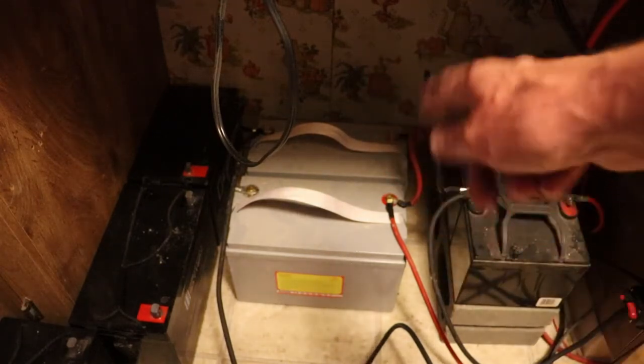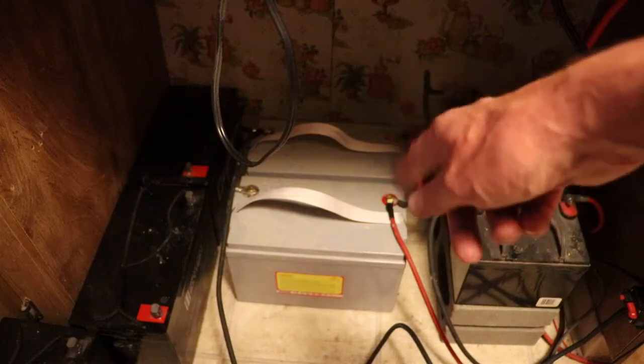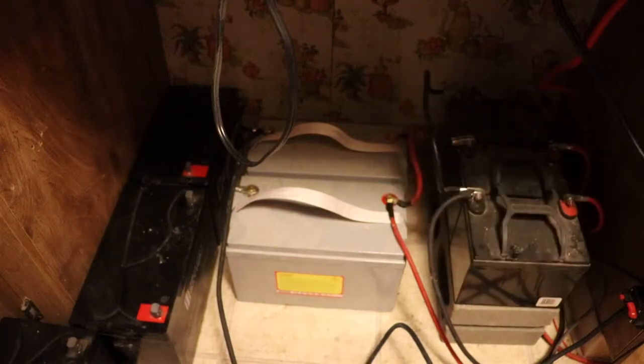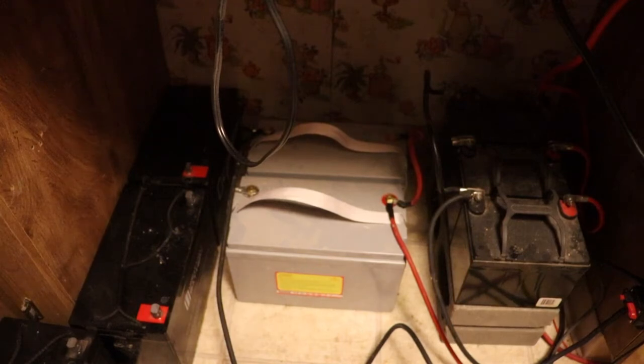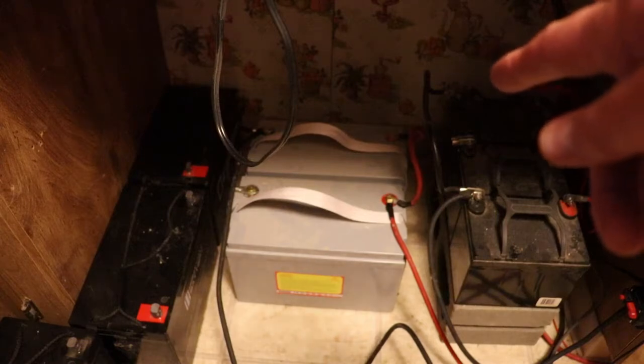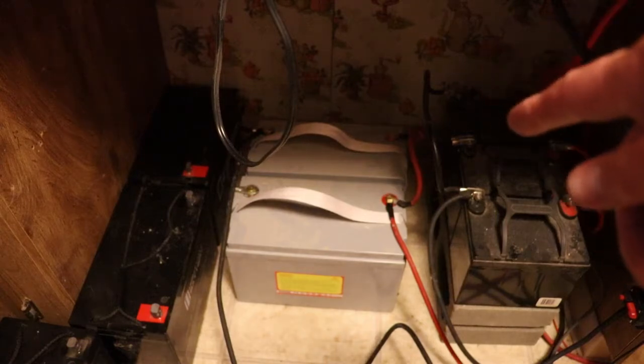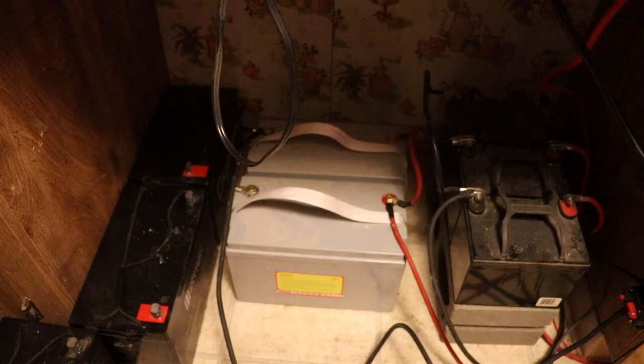I'd have to use almost 5 batteries to replace these 2 batteries for the same amount of charge. Because if you have 5 100 amp hour batteries in parallel, that'd be 500 amp hours, but you're only going to get about 50 to 60% of that, so about 200 to 250 amp hours of usable time. Whereas with just 2 batteries, I'm going to get 180 before I have to recharge.